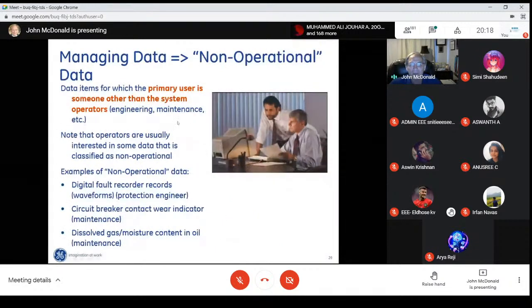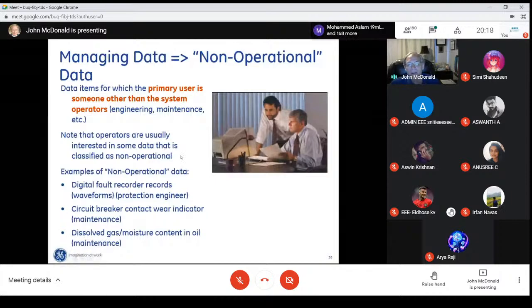The non-operational data is both points and files, data files. The primary user here is someone other than the system operator. And this isn't real-time information, this is on-demand information. So it's called non-operational because the operators aren't interested in it typically. And examples would be like a digitized waveform from a relay that the protection engineer would need. Maintenance information, the circuit breaker contact wear indicator. In a protective relay is the I²T information about the circuit breaker the relay is connected to. Or maintenance information, dissolved gas and moisture content in the oil of the main tank of the transformer that we talked about. So this is both points and files, okay?